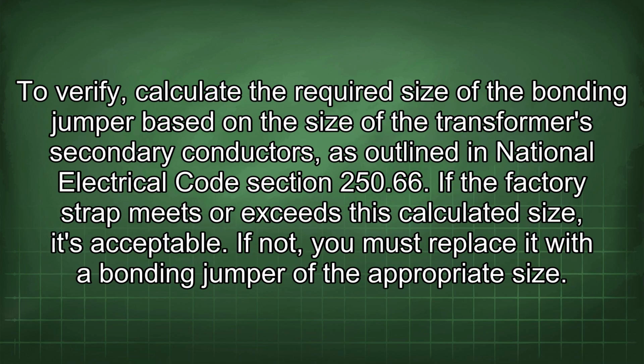To verify, calculate the required size of the bonding jumper based on the size of the transformer secondary conductors, as outlined in National Electrical Code Section 250.66. If the factory strap meets or exceeds this calculated size, it's acceptable. If not, you must replace it with a bonding jumper of the appropriate size.